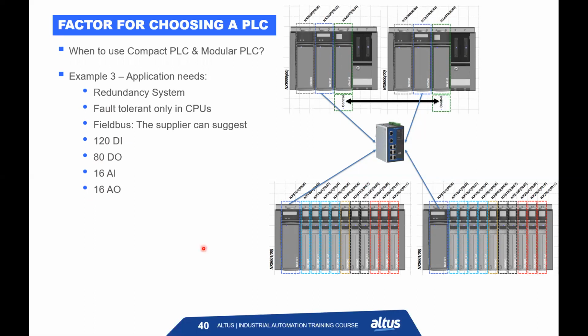The architecture that I created here is exactly our 3030 and X3030 connected in our redundancy coprocessor here, and using Modbus TCP to connect it to 2 slaves here that will feed the CPU with the I/O that is distributed here. So I share this between 2 and put 60 available here, 60 DI here, 60 DI here, 40 here and 40 here, 8 here and 8 here, and 8 analog inputs here, and 8 analog inputs here.